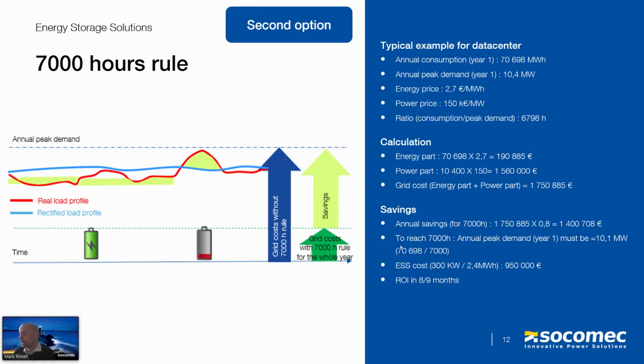We can use and deploy an energy storage solution on the customer site of 300 kilowatts, 2.4 megawatt hours. So a 300 kilowatt system that would last for approximately 8 hours for €950,000, approximately. So you can see on such an installation, the return on investment would be 8 to 9 months through benefiting from an 80% reduction in grid costs would pay for the installation of a battery storage solution.